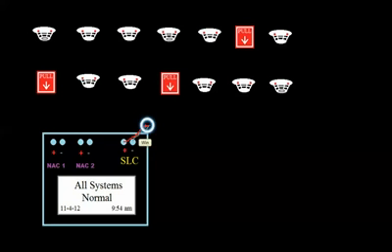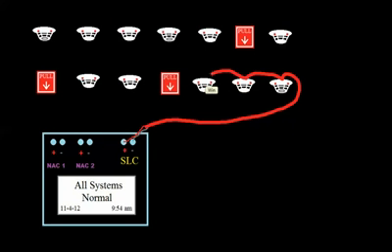So now I'm going to make this a little bit bigger, and I'll just draw this cable, and just imagine that there's a positive and a negative conductor in here, right? So you can wire this up to each device. And now the way that the panel is going to talk to these devices, remember on the conventional system it used current monitoring. So you'd have the circuit, you'd have in and out of each circuit, and then at the end of the circuit you'd have a resistor, right? And it was very important that you go in and out of each device all the way to the end.